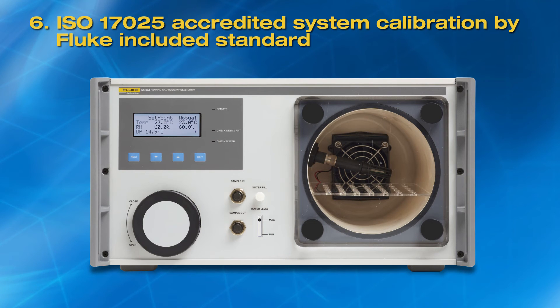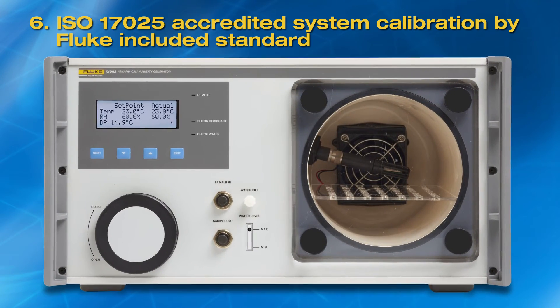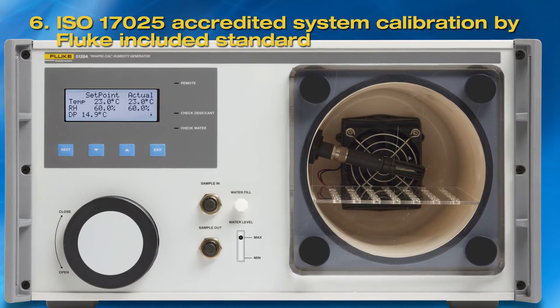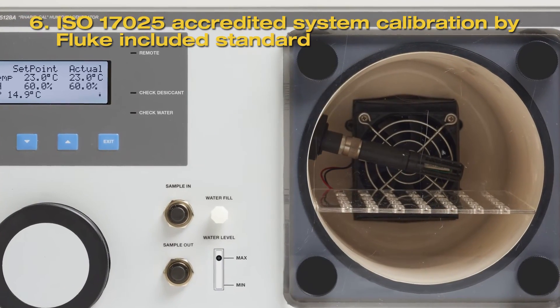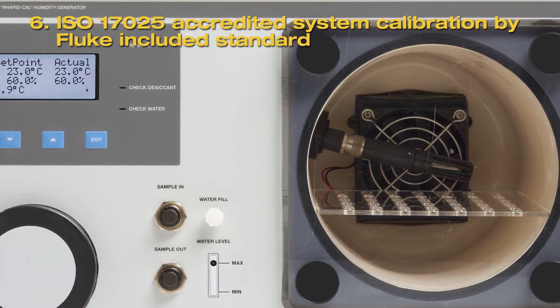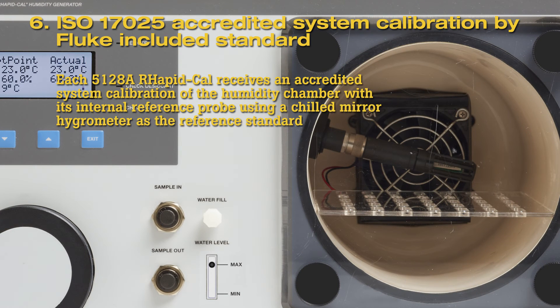Sixth, Fluke accredited system calibration included. Prior to shipment, each 5128A RHapid-Cal receives an ISO 17025 accredited system calibration by Fluke. The humidity chamber, with its internal reference probe, is calibrated using a chilled mirror hygrometer as the reference standard. This system calibration provides the assurance that the 5128A and its internal reference probe have been optimized for the best performance when they leave the factory.